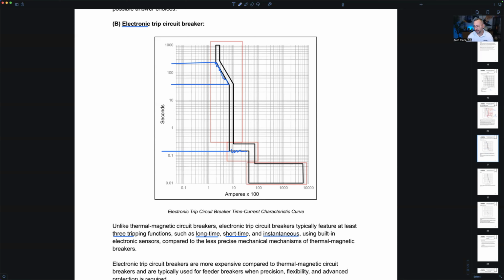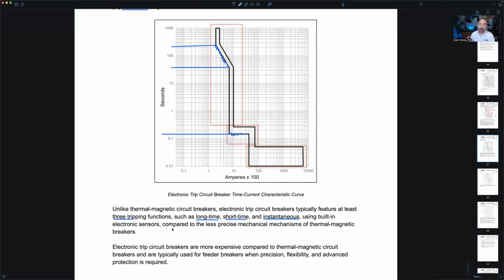They're smart, said Valentina. Ah, Brooklyn. Yes. Brooklyn said because they trip electronically. Yeah. Electronic trip circuit breakers have built-in electronic sensors. So we use electronic sensing devices to trigger the tripping of these breakers. These are not mechanically tripping breakers like thermal mag breakers. These are electronic trip circuit breakers. We've got electronic sensors sensing the current.